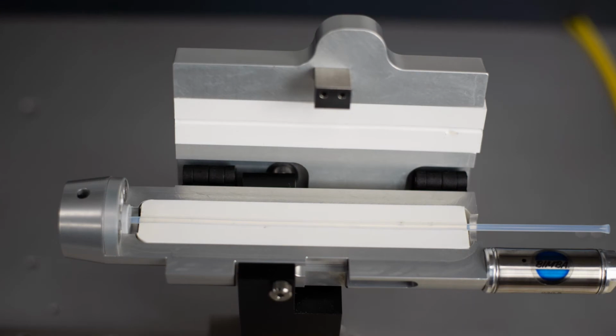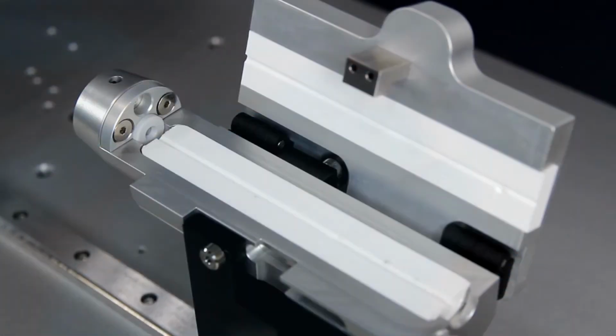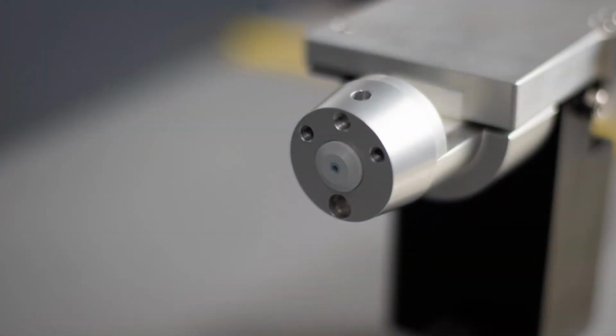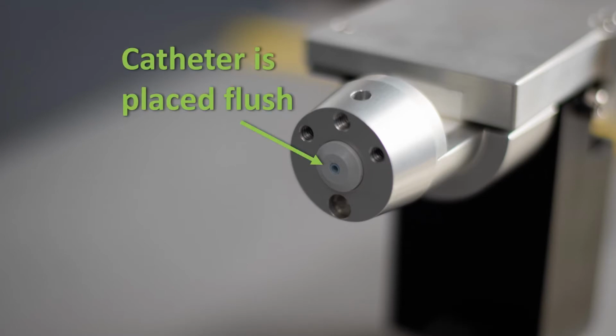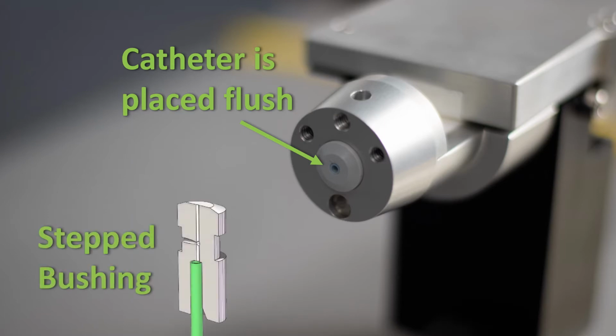With the tooling installed, you can go ahead and place the catheter into the clamshell gripper. First, slide the distal end of the catheter into the alignment bushing. If you have a through bushing, then the front edge of the catheter should be flush with the front of the bushing. If you have a stepped bushing, then you should insert the catheter until you feel it stop against the inside step of the bushing.